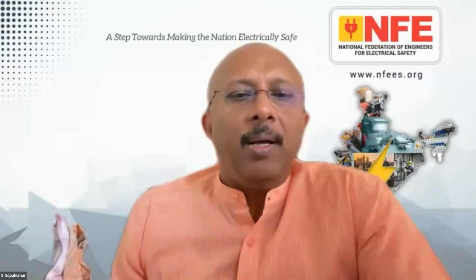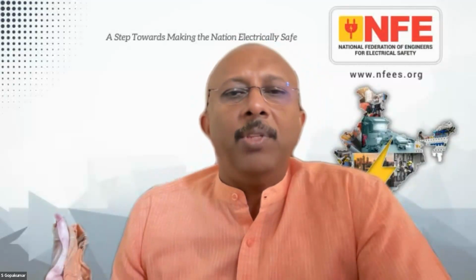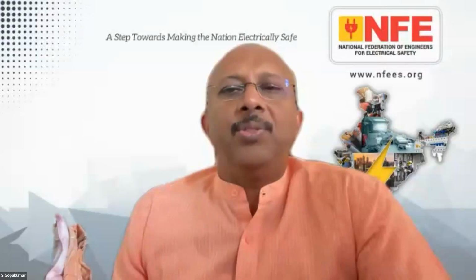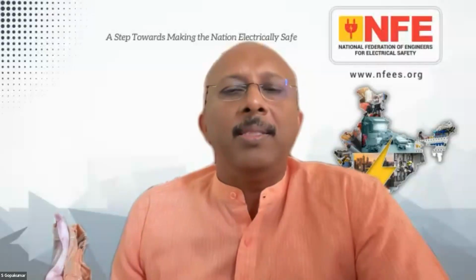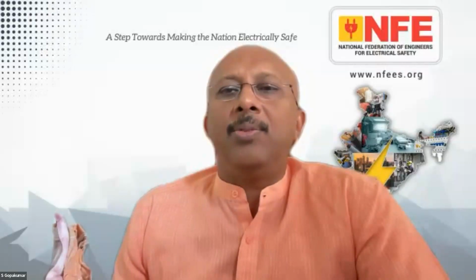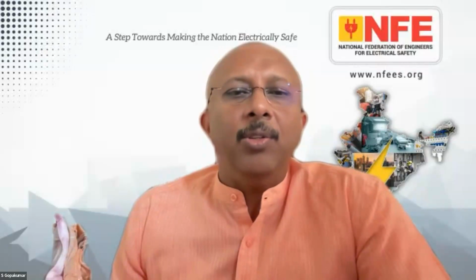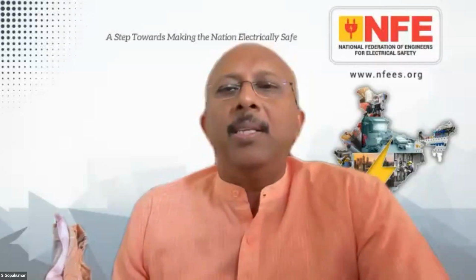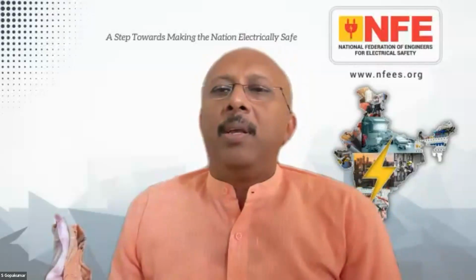So in order to overcome this situation, you have to use a type B RCD, which is not available easily in the market. That is the next challenge. So using an RCD is important, but using the proper RCD is equally important.